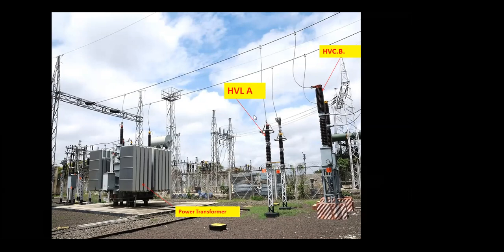I have not gone in detail for equaling load in SCB system - we will discuss that in our presentations. This transformer converts 132 kV here to 25 kV, and you will be surprised, one bushing of this transformer is directly connected to the earth. You will never see this in state electricity board. One terminal is directly connected to the earth, and only one terminal, which is 25 kV single phase, is connected to the overhead system. This is the beauty of this system.